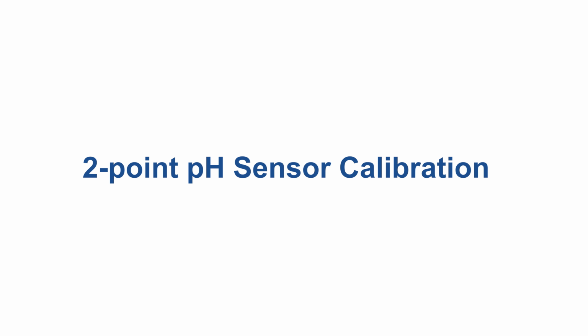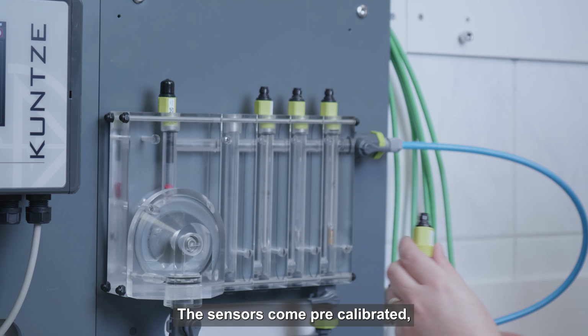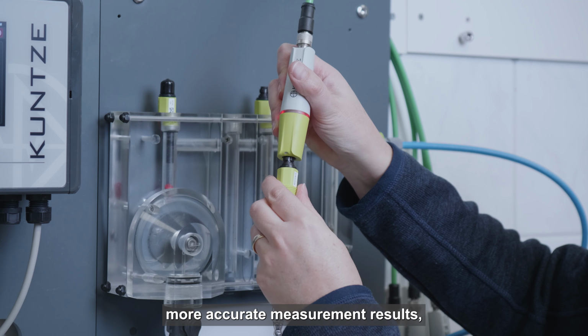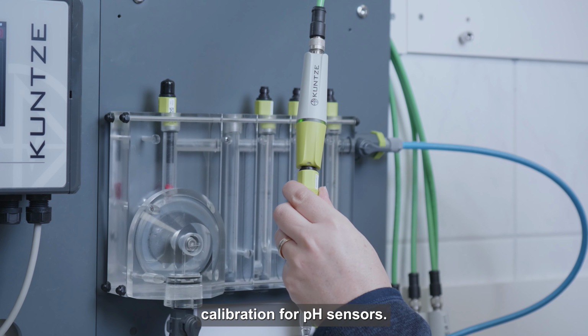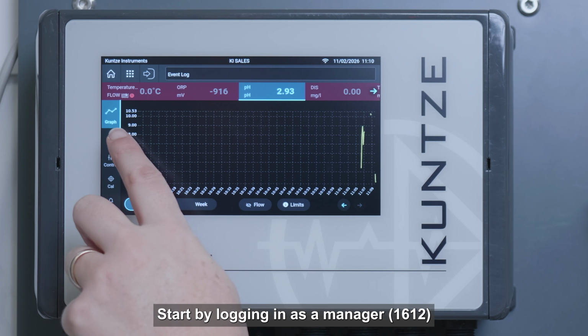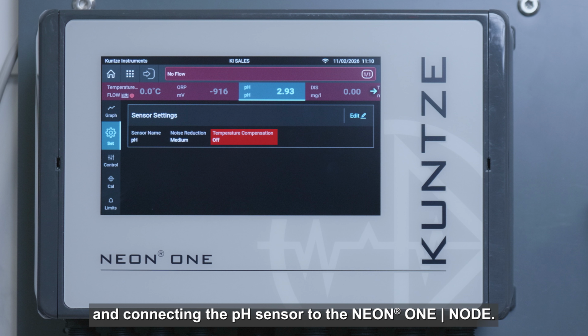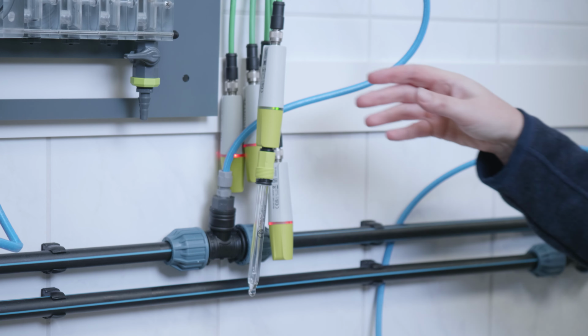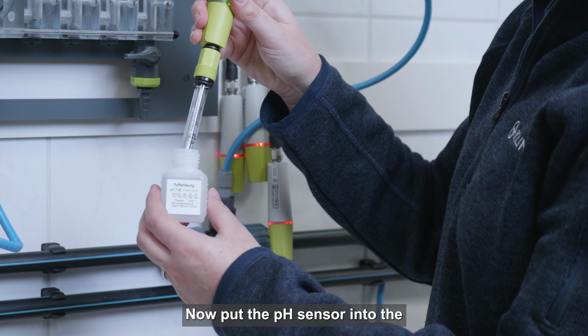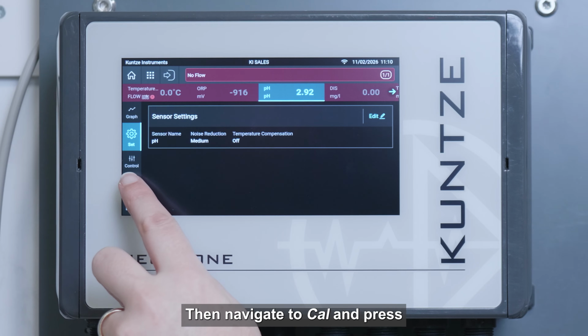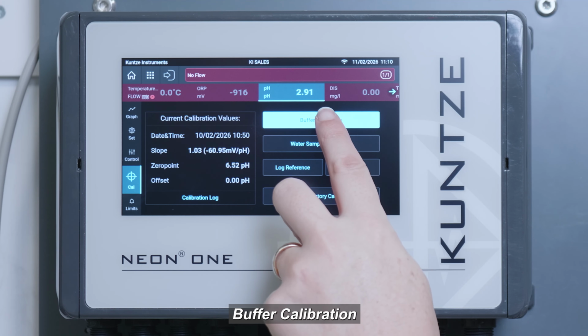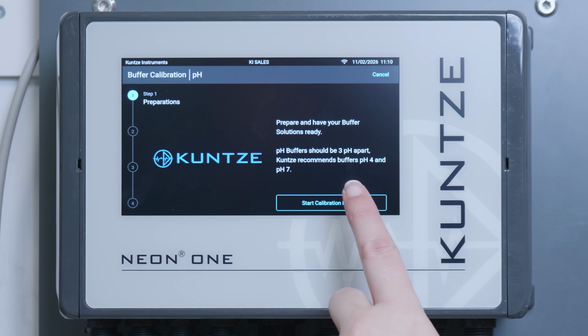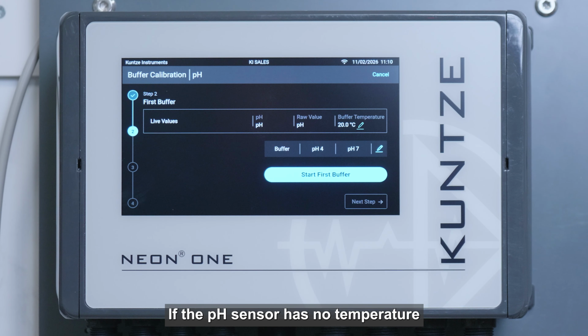2-point pH sensor calibration. The sensors come pre-calibrated, but to ensure more accurate measurement results, we recommend to do a 2-point calibration for pH sensors. Start by logging in as a manager and connecting the pH sensor to the Neon ONE node. Now put the pH sensor into the pH 7 buffer. Then navigate to Cal and press Buffer Calibration and start the calibration routine. If the pH sensor has no temperature probe included, set the temperature compensation to manual mode and change the buffer temperature here manually if needed.